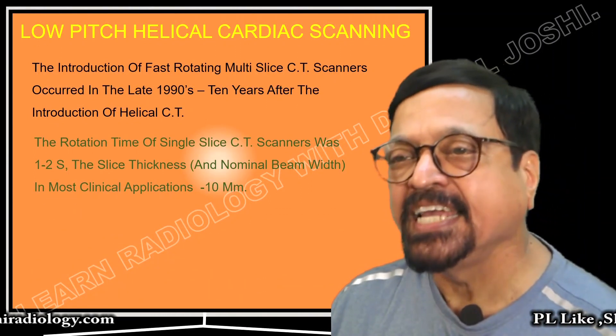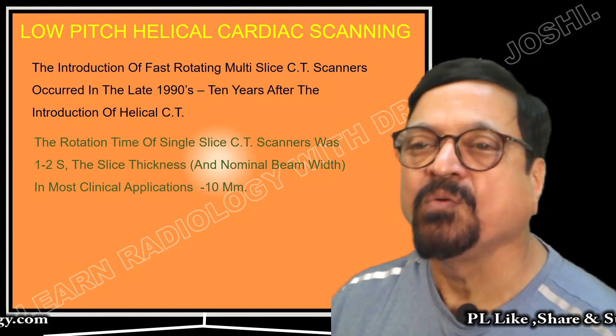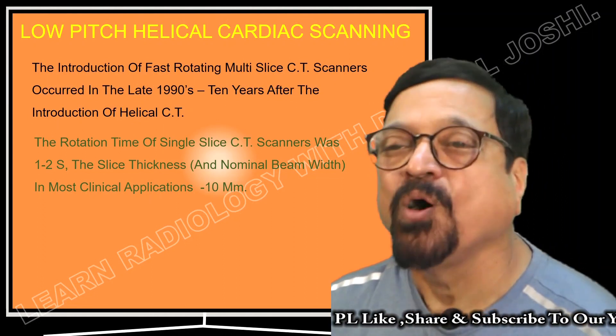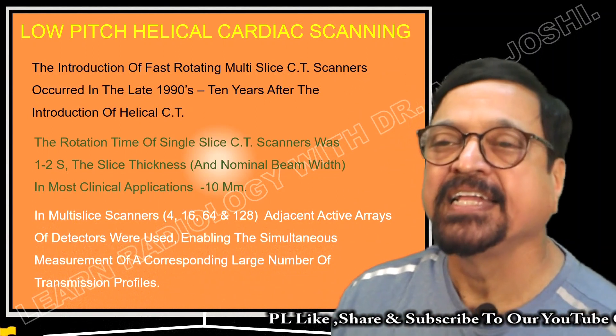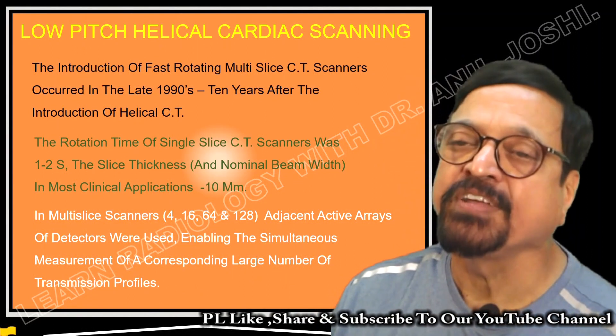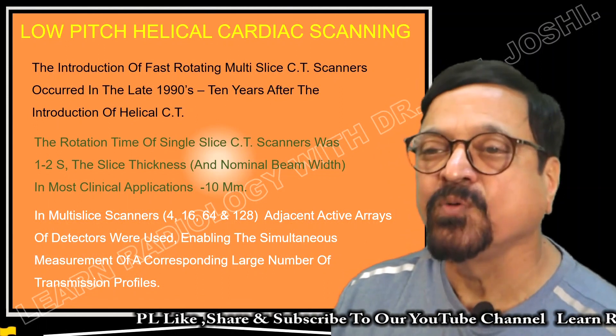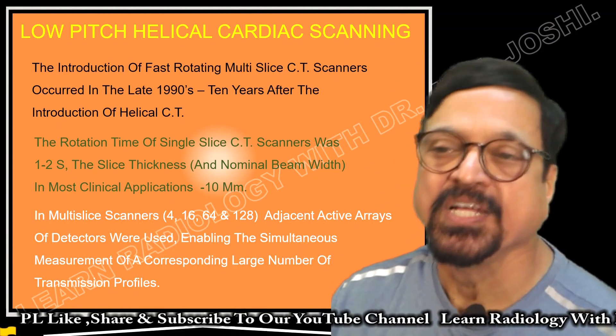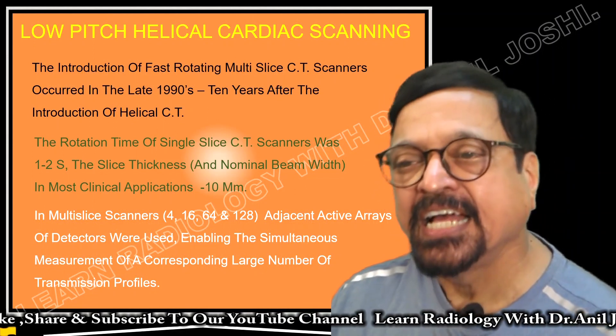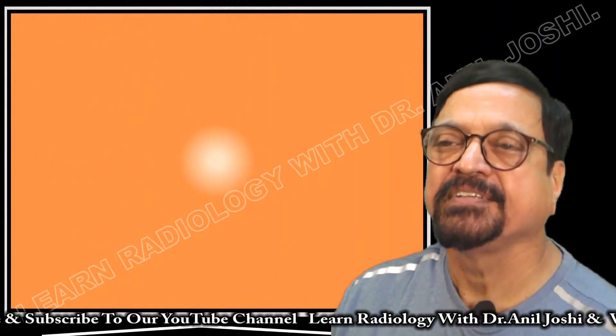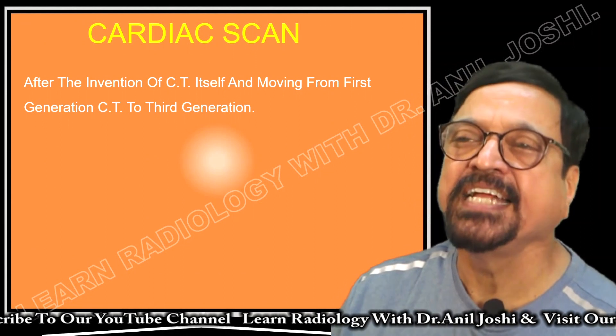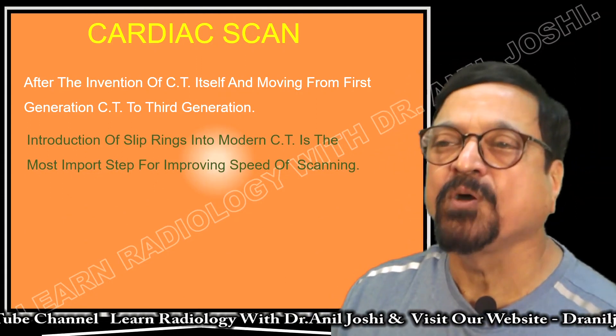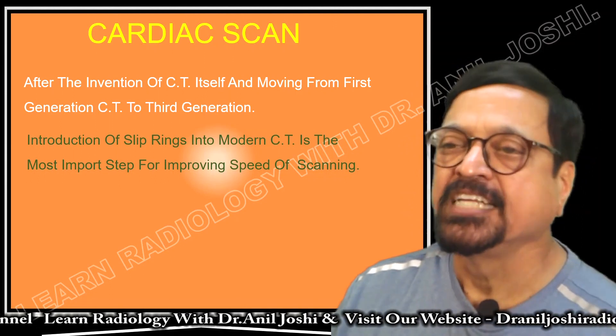The rotation time of a single-slice CT scanner was 1 to 2 seconds, with slice thickness of around 10 mm. Almost the entire body was covered in a single breath — less than 1 second to 1.5 seconds. In multi-slice scanners — 4, 16, 64, 128 — adjacent active arrays of detectors are used, enabling simultaneous measurement of a large number of transmission profiles. Cardiac scanning moved from first generation CT to third generation faster. Introduction of slip rings into modern CT scanners was the most important step for improving scanning speed.